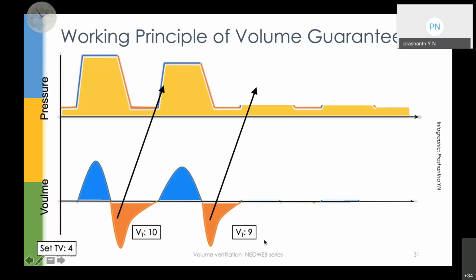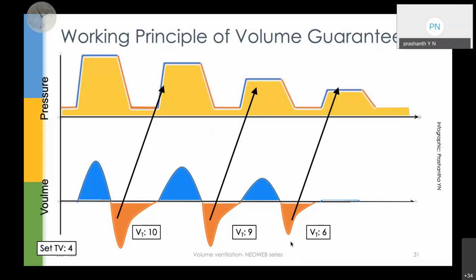And now the ventilator again thinks, okay, is it sufficient? No, it is not sufficient. It is too high for this baby. Let me decrease the pressure again. And then the pressure decreases, and from the feedback you see the tidal volume again decreases for the next breath. So if you observe this, from 10, it is intelligently guessing what the pressures could be, going in a smooth forward direction, giving feedback with each breath, and going down. So from 10 to 9 to 6, by decreasing the pressures, it is doing all the work itself. I am not involved in anything in this. All I have done is set a tidal volume of 4 and let the ventilator work on its own. Once your tidal volume is 6, it again realizes that it is more, gives feedback, and decreases again. And then there you go, you get your tidal volume of 4.